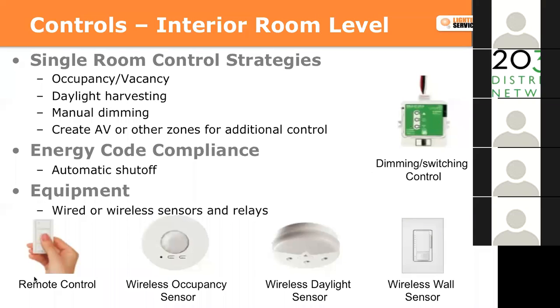This slide, again, you've probably seen most of what's on here, but controlling the lighting and adding functionality to a space doesn't require a fully networked system. You can use a combination of standard occupancy or vacancy sensors. Vacancy is probably more popular now due to code, meaning you actually have to turn it on - it's not like a wall switch where you walk in and lights turn on automatically. With a vacancy sensor, you walk in, turn it on, and then it automatically shuts the lights off. That prevents false offs as people would walk by an office or a room.